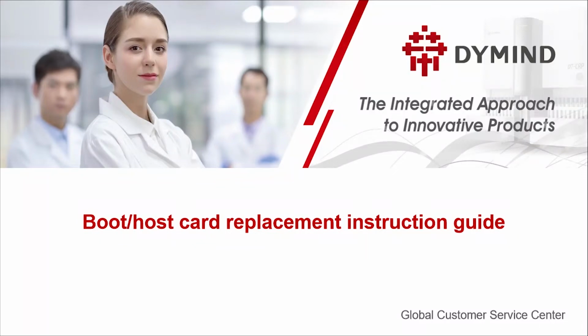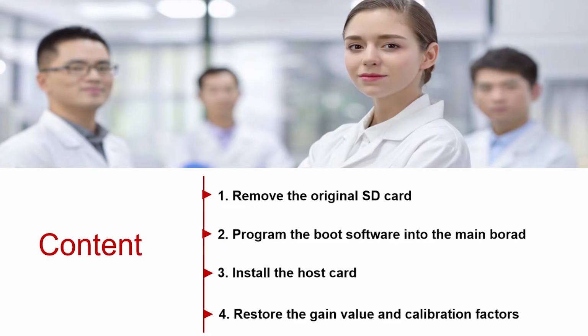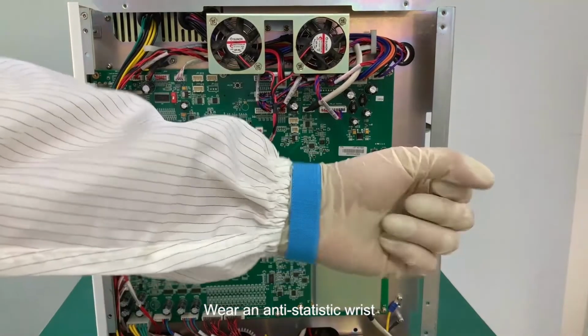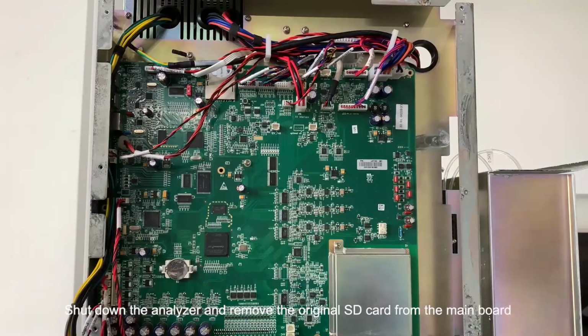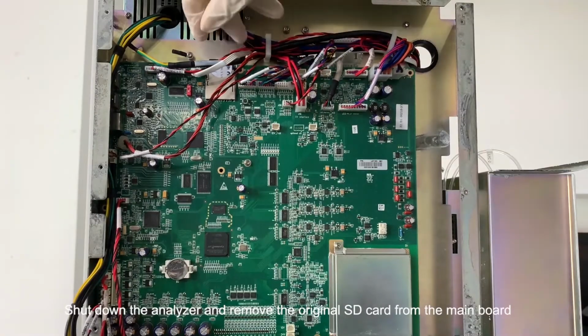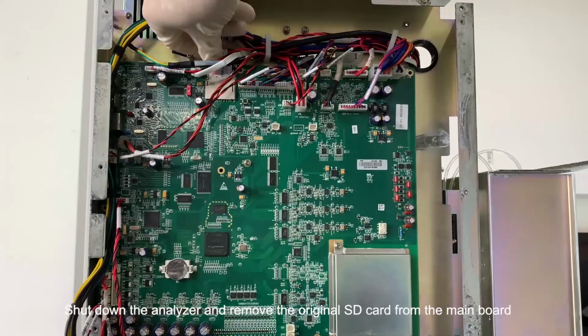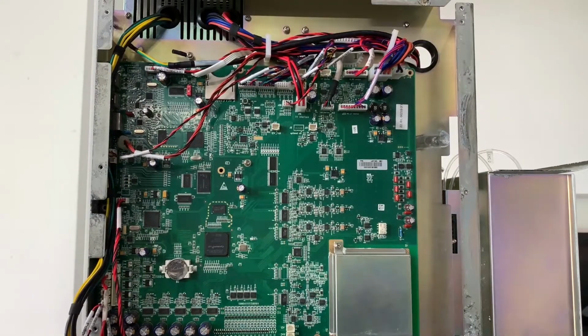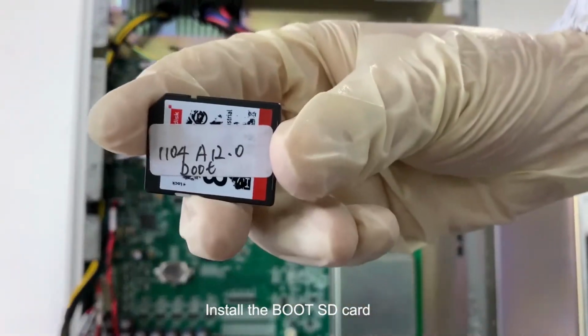This video shows how to replace the boot and host SD card. Wear an anti-static wrist strap. Shut down the analyzer and remove the original SD card from the main board. Install the boot SD card.